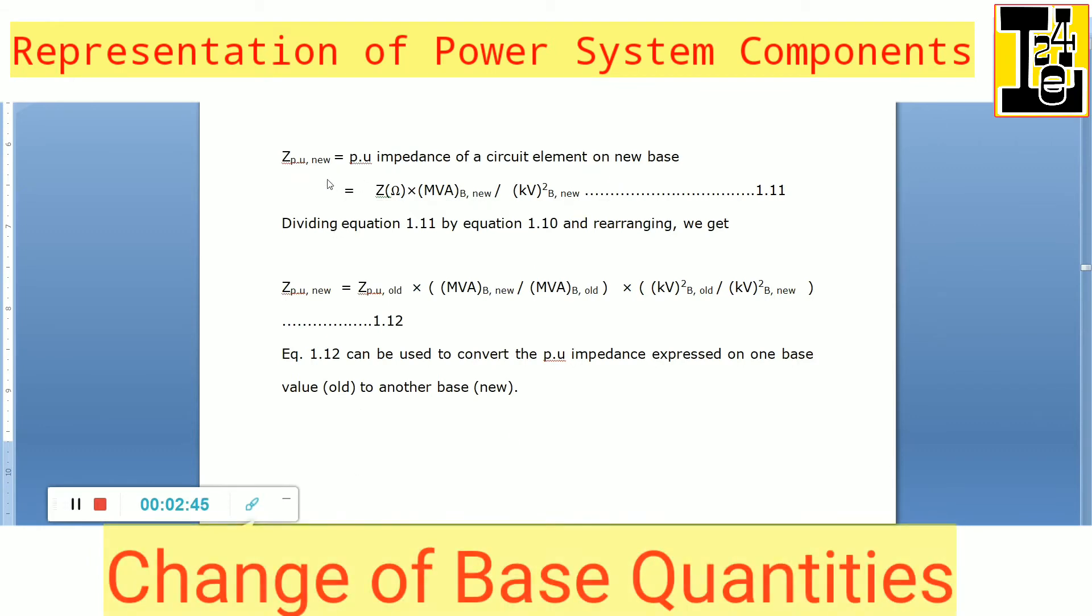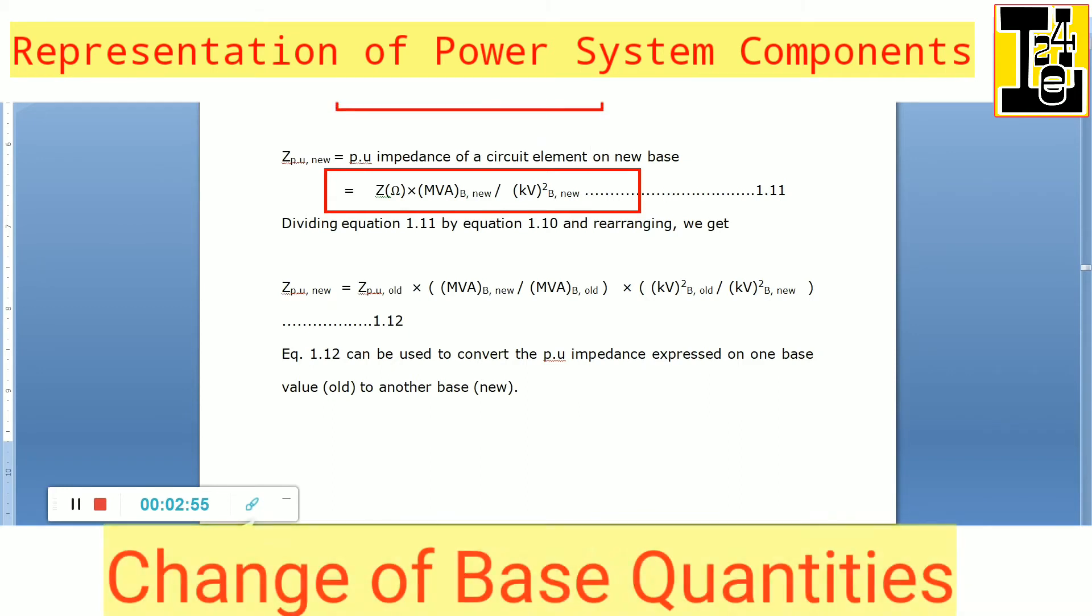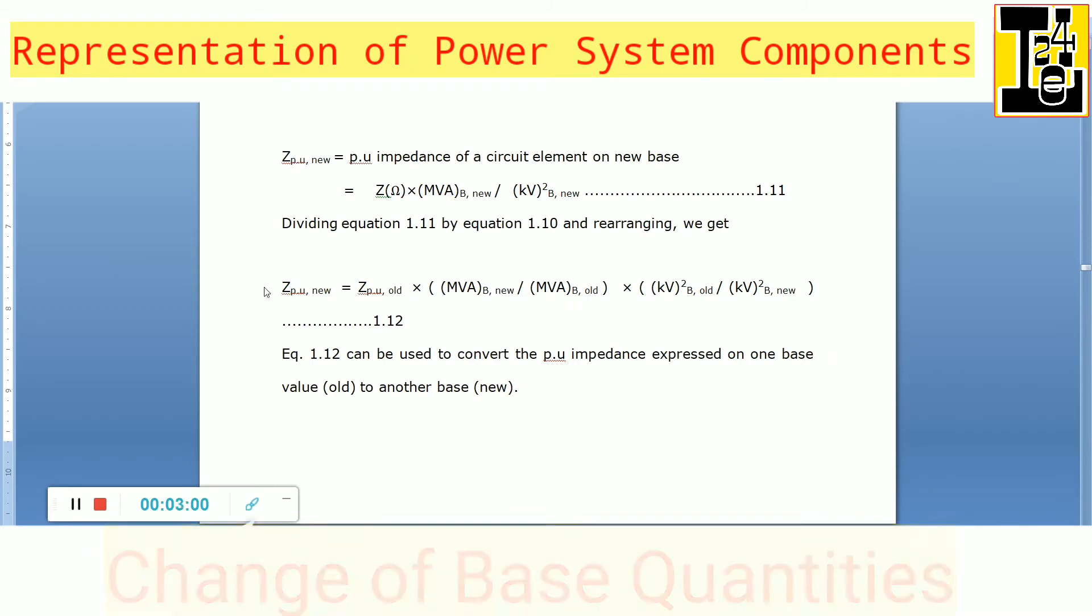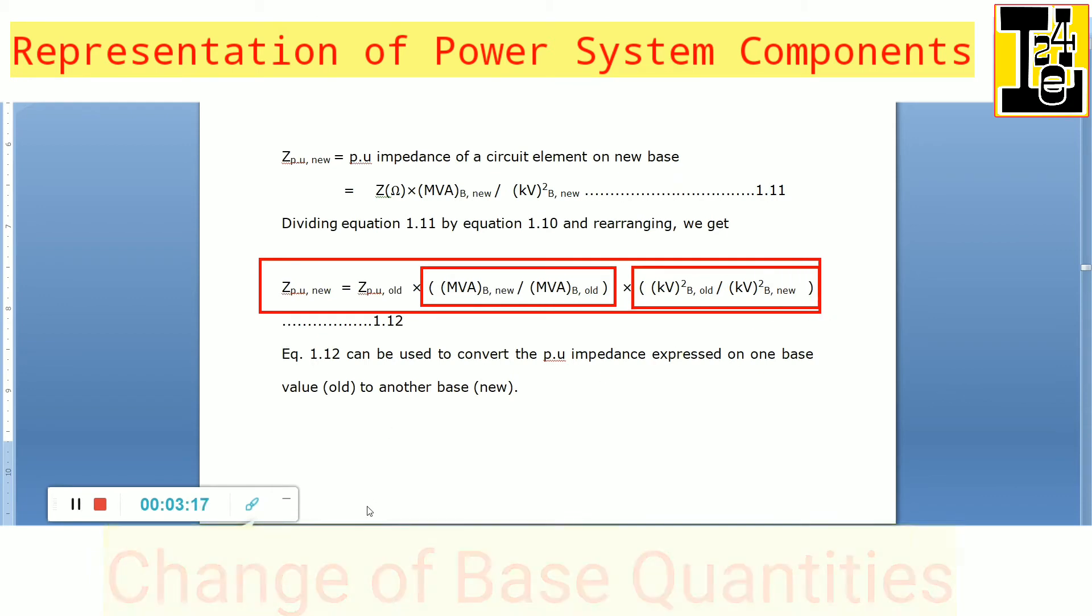So, dividing this expression Z per unit new by Z per unit old and rearranging the expressions, we will get Z per unit new equals Z per unit old into MVA base new divided by MVA base old into KV base old square divided by KV base new square.